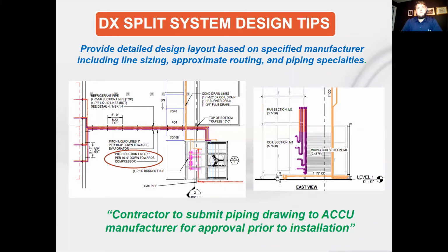The only thing we found wrong with it was, well, there were some other things on other pages, but on this particular page, the suction lines were pitched the wrong direction. Trane now recommends that you pitch the pipes away from the compressor so that the oil doesn't come back in a big slug, because there's not that much oil in these compressors anymore. So that's really one of the few things we found. But the good news is that we found this on paper and not on a field inspection after it was all piped up.